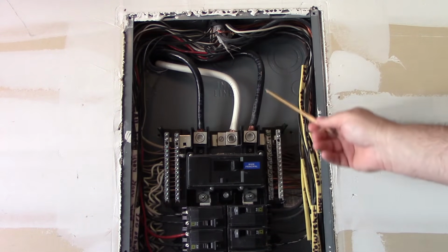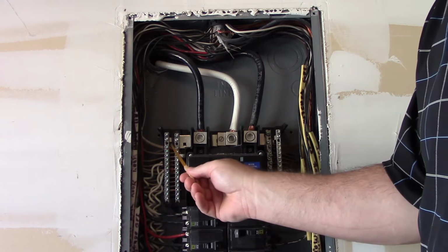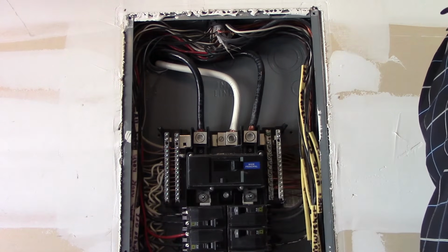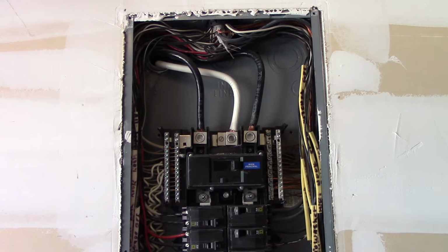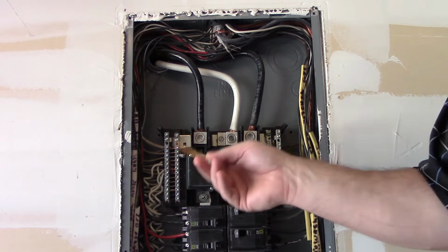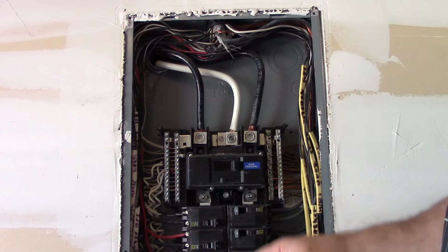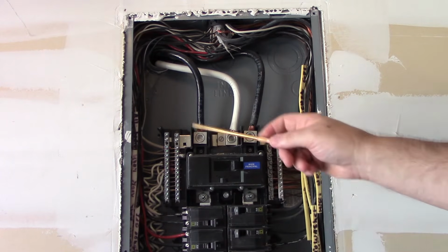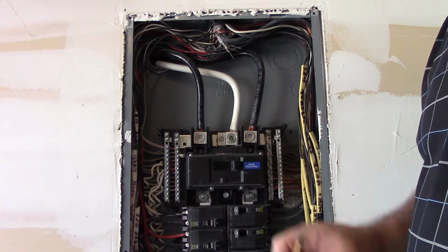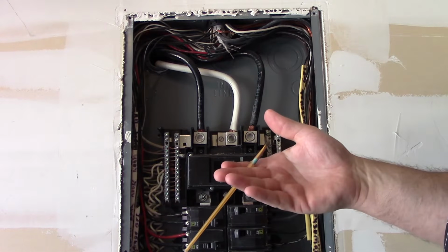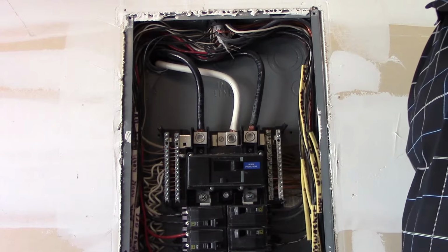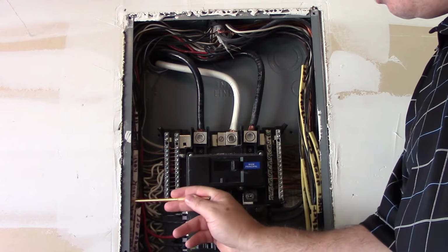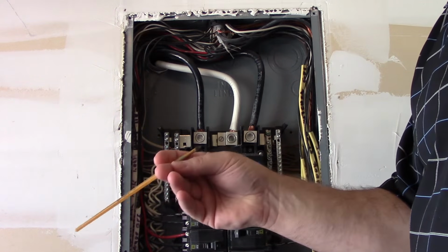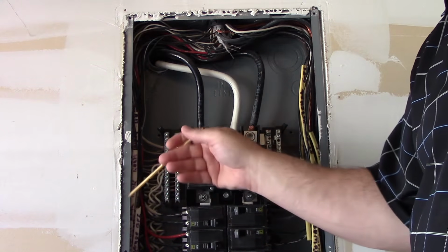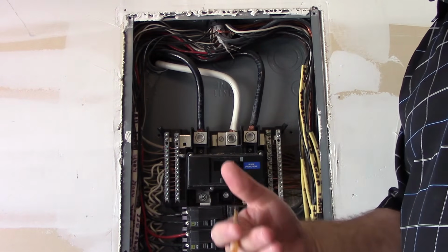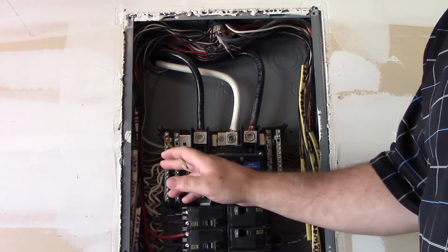All right. Now, as I move down to the grounded terminals, I want to make sure that I only have one grounded conductor per terminal. That's in accordance with 408.41 of the National Electrical Code, but it goes deeper than that. It also goes back to 110.3(B), which says you have to install this panel in accordance with the instructions. UL 67 governs this panelboard and all the componentry that goes along with it, remembering that we're dealing with a cabinet here and the panelboard in the middle, and under UL 67 it did not permit this. So under 110.3(B) of the National Electrical Code you have to install this in accordance with the instructions. The instructions, even the identification in this legend over here, say nothing about multiple grounded conductors sharing a terminal. It does talk about it for the equipment ground, but it doesn't give you any permission to do it over here. So it was not allowed long before the National Electrical Code incorporated 408.41 into it. There is your evidence of why these need to be under a single termination.